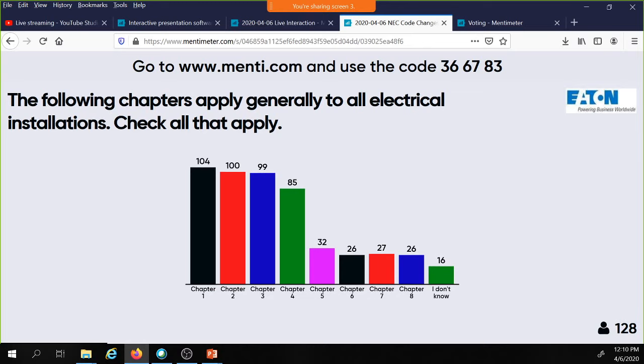All right, so chapters 1 through 4, and we're going to talk about Article 90 of the National Electrical Code, 90.3 is your reference for this one. 90.3 tells us that chapters 1 through 4 apply generally to all electrical installations. When you get into chapters 5, 6, and 7, those chapters focus on either special occupancies, special equipment, or special conditions. So 5, 6, and 7 do not apply generally to all electrical installations. They will only apply to the installations that are under their purview.